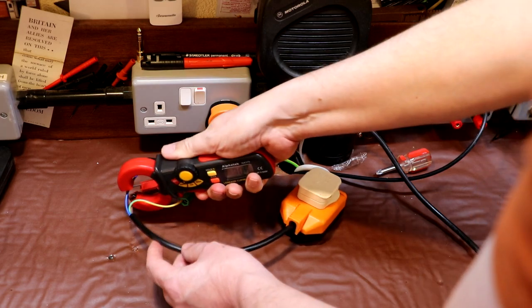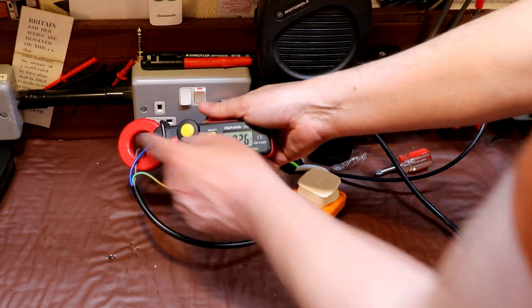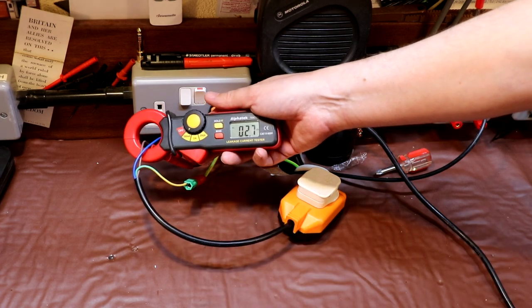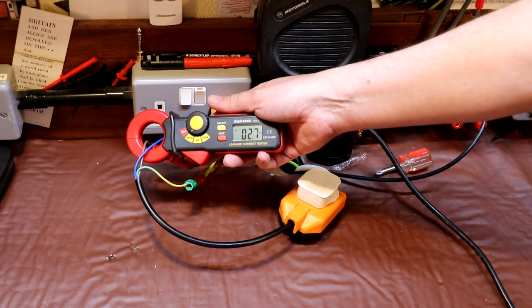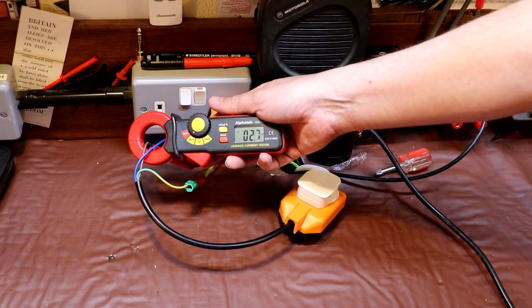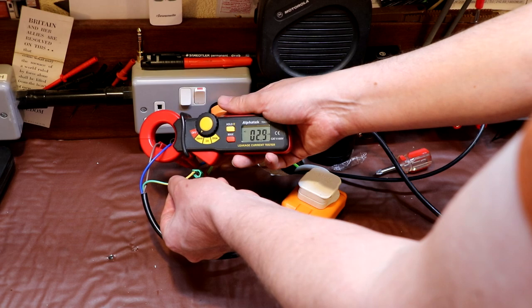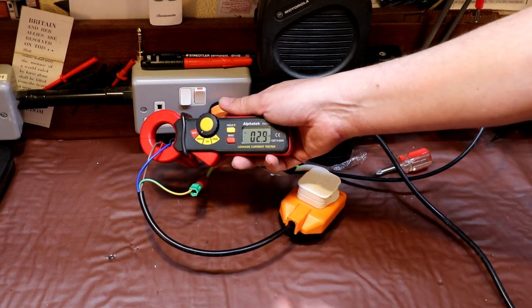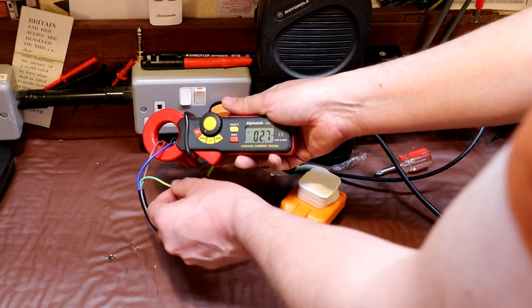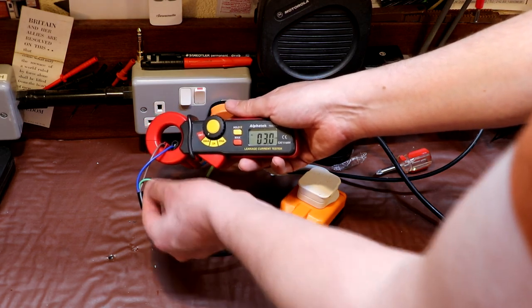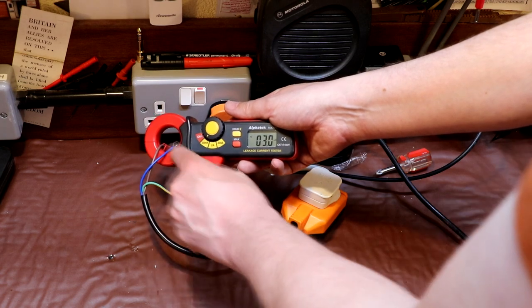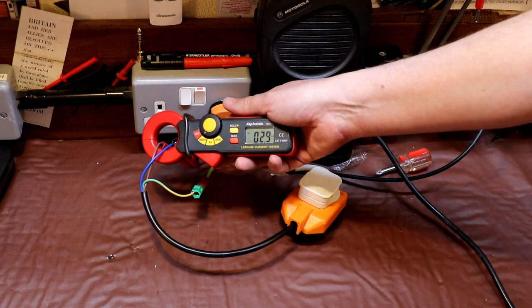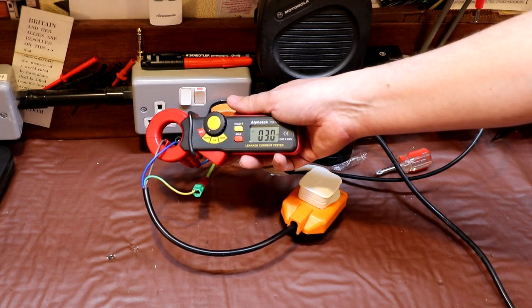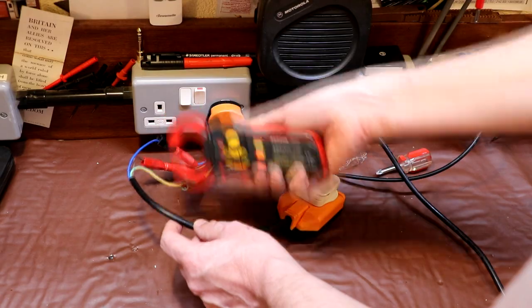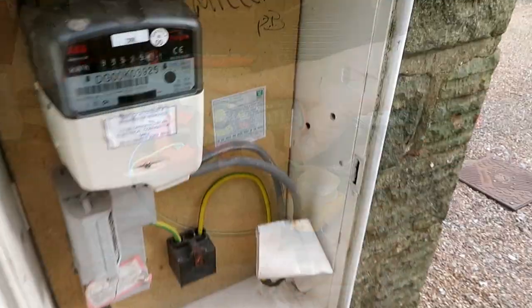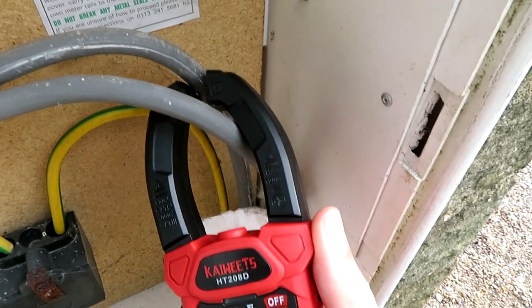For those of you wondering why I prefer to put the meter around both the live and the neutral wires to measure the imbalance, it's because for a piece of equipment that's manufactured from metal, some of that residual current might not be flowing down the earth wire. If it's a piece of metal bodied equipment sat on the floor, some of that earth current could be going directly into the floor, in which case it won't be flowing down the earth wire, but you will still see the imbalance if you measure between the live and the neutral, as I did here. So if you're looking for earth leakage currents, this is a better way of doing it than just monitoring the current in the earth wire itself.